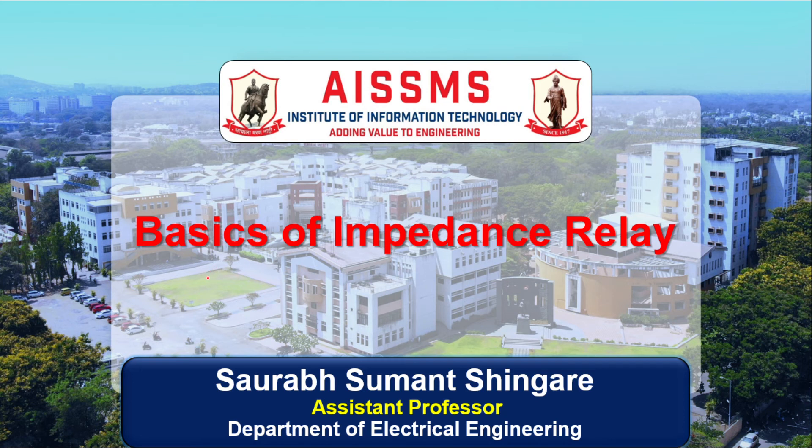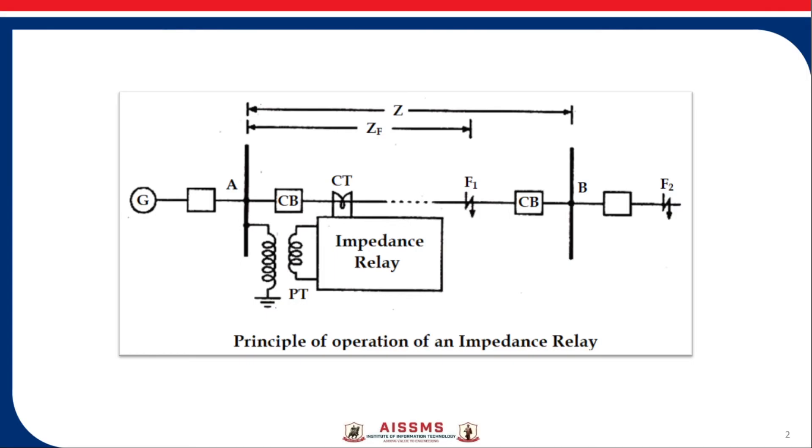In distance relays the operation is dependent on the ratio of voltage and current which is expressed in terms of impedance. Hence basically distance relays are called impedance relays. The impedance is the electrical measure of distance along a transmission line. This is also called as ratio relays.